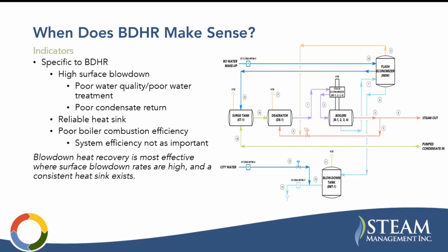Specific to blowdown heat recovery, I would say a high surface blowdown rate, which is going to be driven by poor water quality or poor water treatment, or poor condensate return, as we'll see in our example in a minute. All of your dissolved solids, or most of them, are being introduced through your makeup water. If you require a lot of makeup water due to a poor condensate return rate, that can really drive up the dissolved solids in your boiler that have to be removed. So that can drive up your blowdown rate.